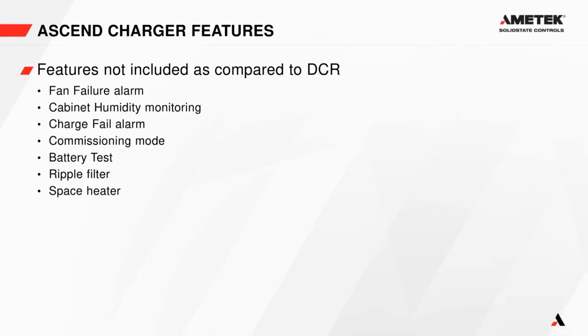Some features that are not included in the Ascend that were included in the DCR are cabinet fan failure alarms or heatsink fan failure alarms. We don't have cabinet fans in the charger, and if the module fans fail, you'll get an over temperature alarm instead of a fan failure alarm. We have not included cabinet humidity monitoring. We don't have a charge failure alarm. And we don't offer commissioning mode anymore.